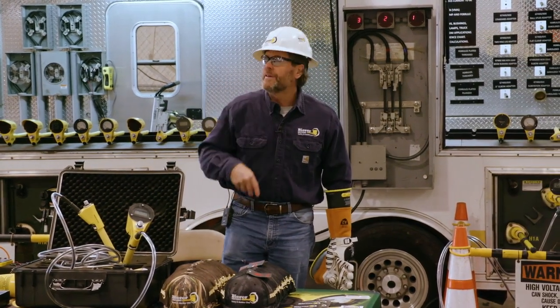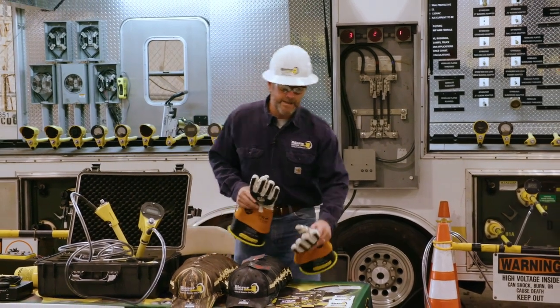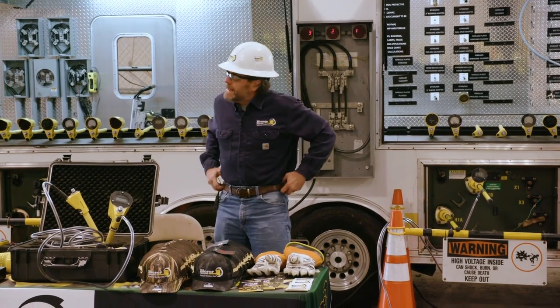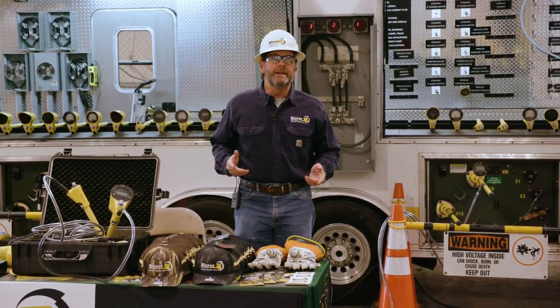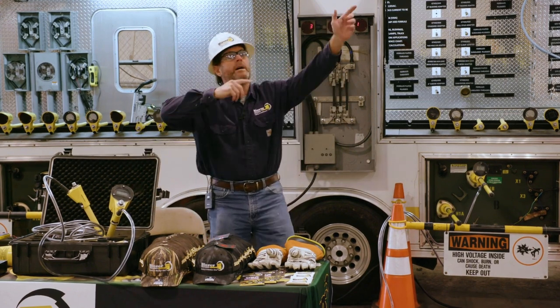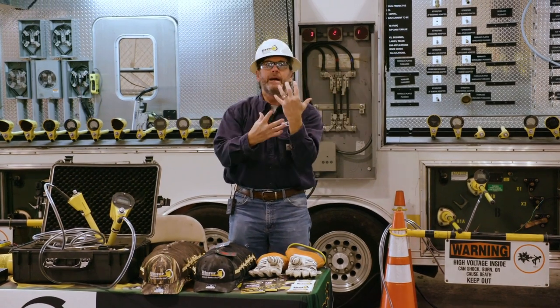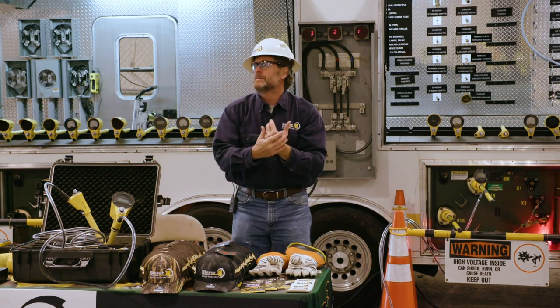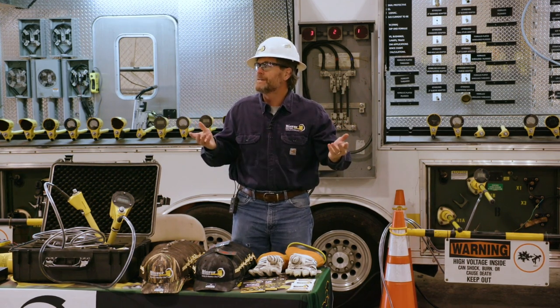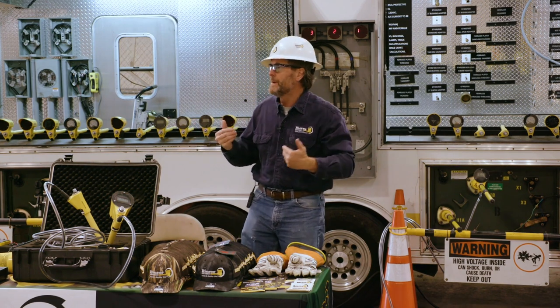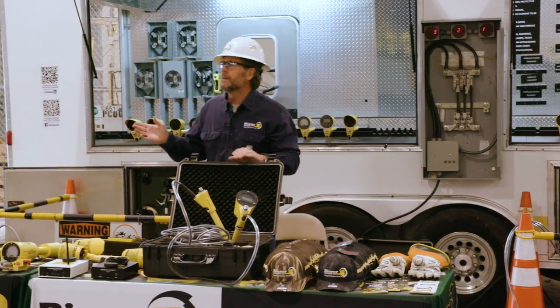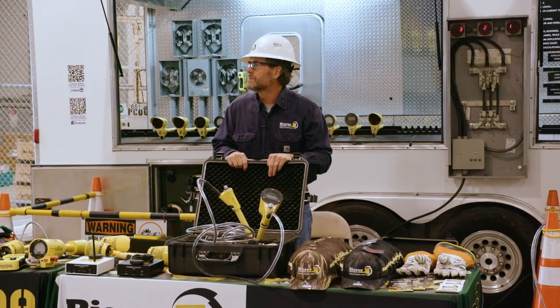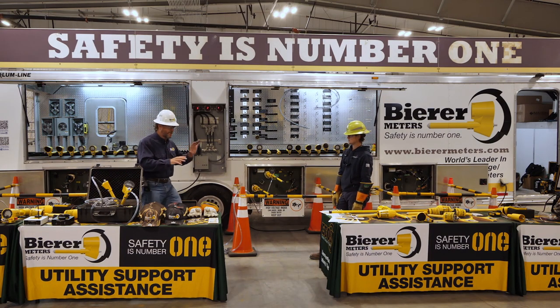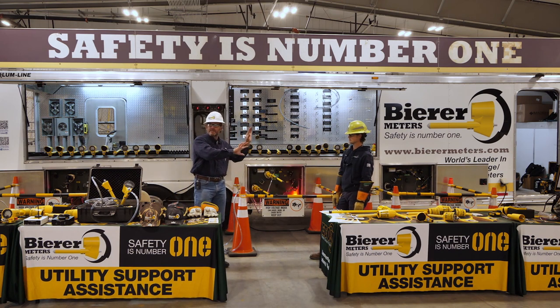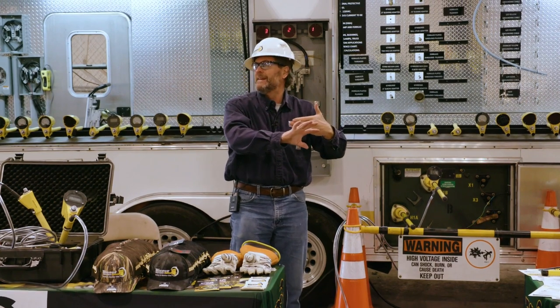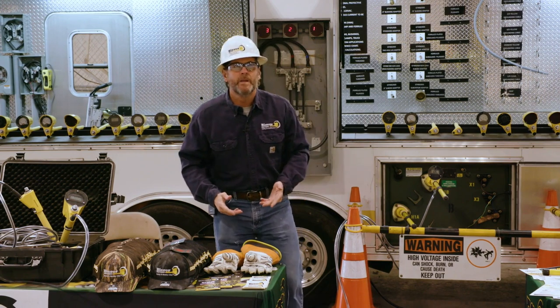So I got a call from a utility in Texas. They had a couple of guys working in a substation at a cooperative. When they were using the corded tool, they were on a hot phase, and the meter head was close to another hot bus. So what do you think happened? They had an arc flash, right? And that's what happened. They called the shop and said, hey, your tool's no good, we need to get a replacement, maybe we need to start using somebody else's tools. So they showed us the photo, and sure enough it showed the tool making contact. The hot bus is next to the meter head here, and the meter is almost against it. So no one had ever trained them on how their tools function. They didn't know, so they had an arc flash.